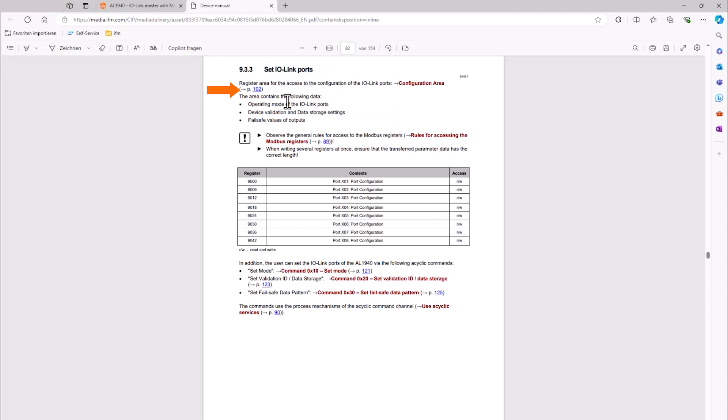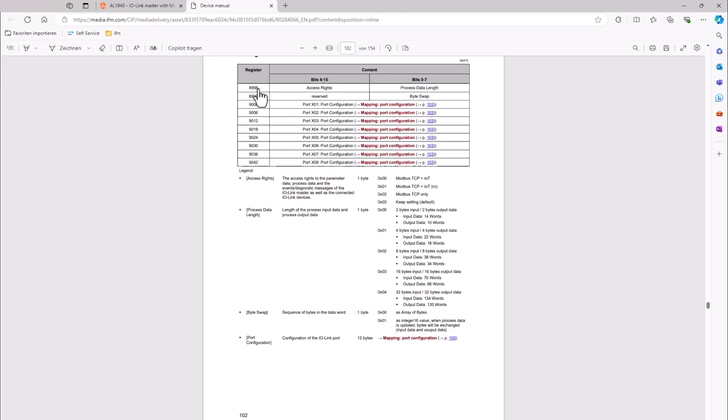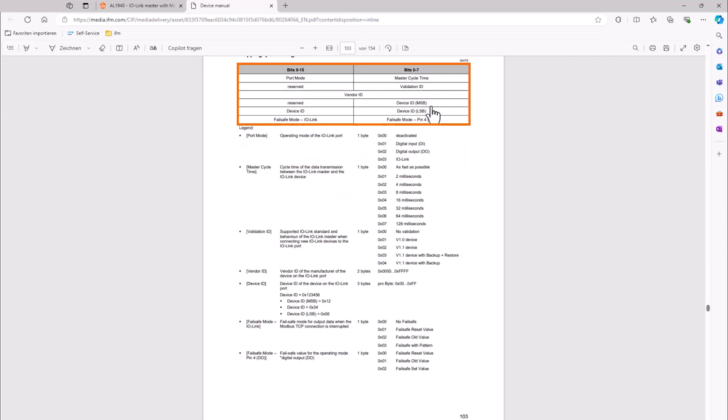We open it and navigate to the Modbus TCP section and select Set IO-Link ports. Then go to the Configuration area. Here we can see that the register for the configuration of port number 1 starts with 9000. Select the mapping for this port, because this is where our IO-Link sensor is connected to.